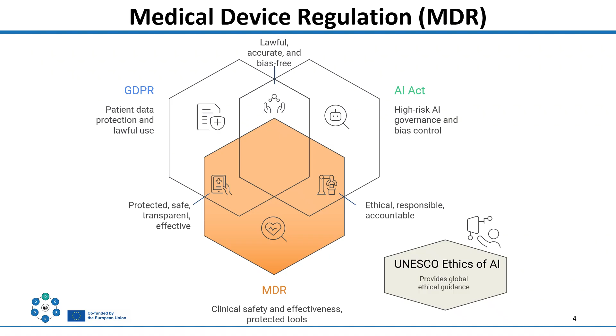The Medical Device Regulation, MDR, governs the placing on the market, making available and putting into service of medical devices within the European Union. Its scope includes a broad range of products, from traditional medical devices to certain software and AI-based systems intended for medical purposes, as well as post-market surveillance and vigilance obligations. It establishes requirements for safety, performance, clinical evaluation, conformity assessment, and CE marking to ensure a high level of protection for patients and users.